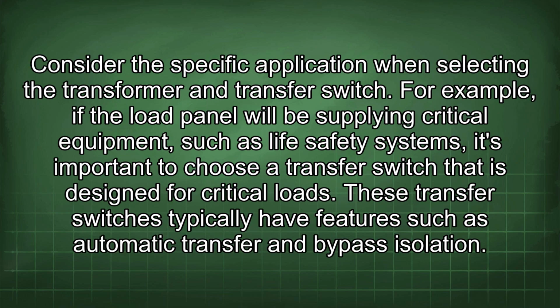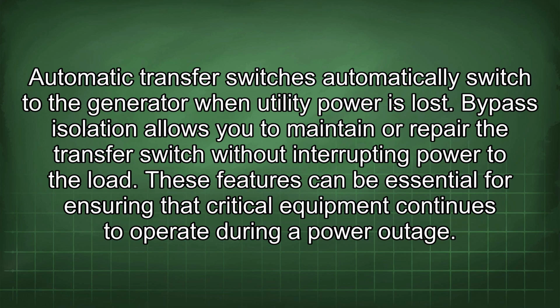Consider the specific application when selecting the transformer and transfer switch. For example, if the load panel will be supplying critical equipment, such as life safety systems, it's important to choose a transfer switch that is designed for critical loads. These transfer switches typically have features such as automatic transfer and bypass isolation. Automatic transfer switches automatically switch to the generator when utility power is lost. Bypass isolation allows you to maintain or repair the transfer switch without interrupting power to the load. These features can be essential for ensuring that critical equipment continues to operate during a power outage.